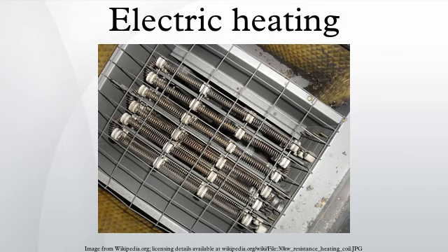Water immediately adjacent to the heating element is heated to a temperature which is high enough to promote the formation of scale, commonly calcium carbonate, in hard water areas. This accumulates on the element, but over time, as the element expands and contracts through its heating cycle, the scale cracks off and drops to the bottom of the tank, progressively filling up the tank.